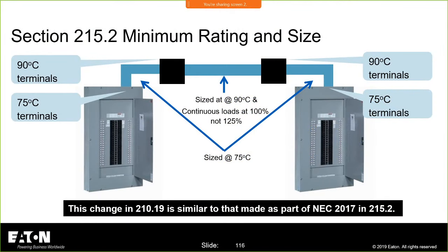Actually, I'll just go straight to the picture and we'll end on this one. This is permitting the sizing and use of this conductor at its 90°C rating and at 100% when you land it on these two enclosures with properly rated terminals and lugs. I would argue that the National Electrical Code did not need to include this, because you could have done this under the current rules. This just raised the awareness that it can be done, and I would argue that the length of this conductor would have to be pretty doggone long to justify two large enclosures on the outside of these panel boards. That would have to be pretty doggone long. But anyway, I'll let that one sink in.